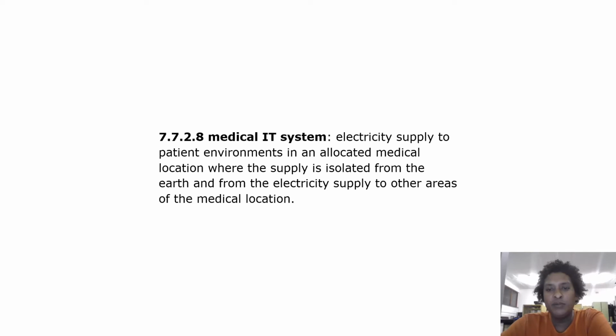Medical IT system. Electricity supplied to patient environments in an allocated medical location where the supply is isolated from the earth and from the electricity supply to other areas of the medical location.